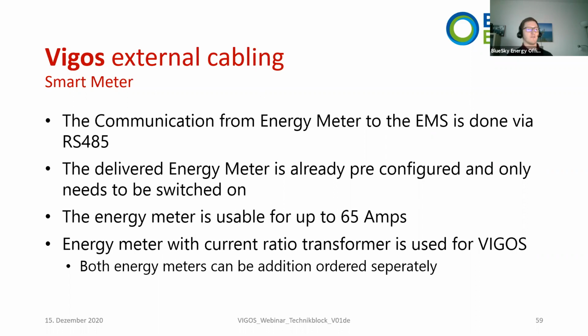The energy meter is usable for up to 65 amps inside the cell 3050 system, and for the Vigos system, you will receive an energy meter with current ratio transformers. The transformers themselves are not part of delivery, but the input current is 5 amps. So the input current of the energy meter for transformers is 5 amps, but please organize the transformers yourself. If you have, for example, 200 amps input current, organize a transformer with a 200 amps input current and 5 amps output current.